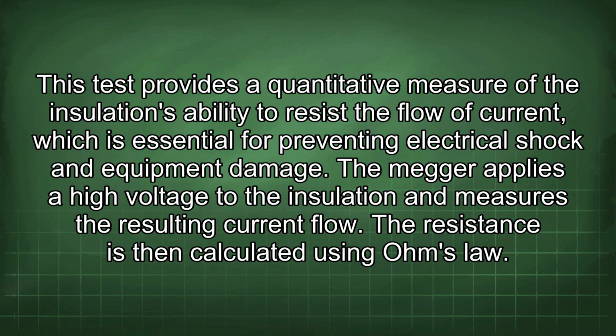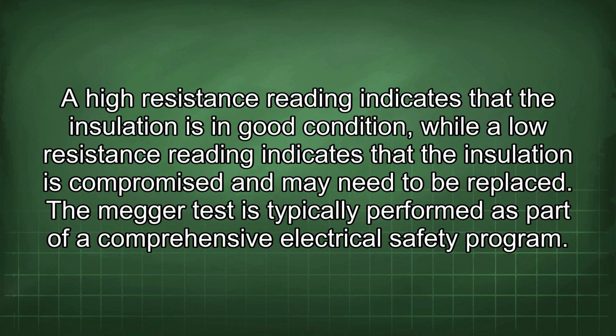The megger applies a high voltage to the insulation and measures the resulting current flow. The resistance is then calculated using Ohm's law. A high resistance reading indicates that the insulation is in good condition, while a low resistance reading indicates that the insulation is compromised and may need to be replaced.